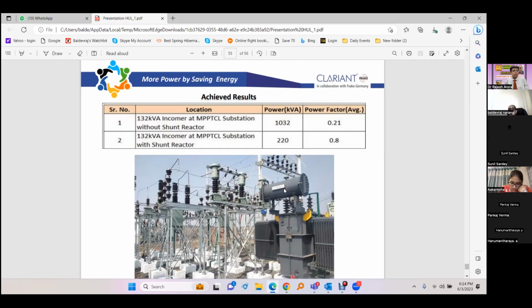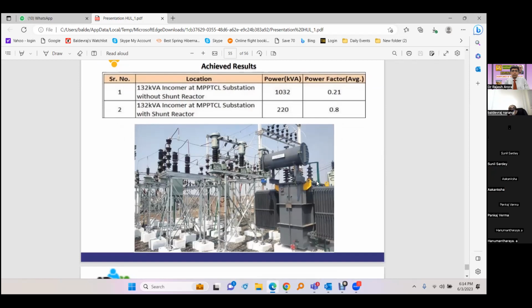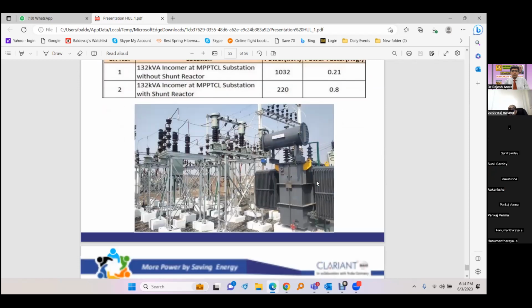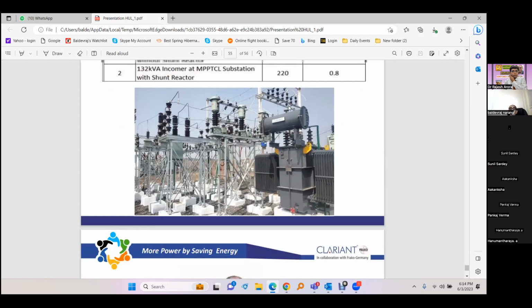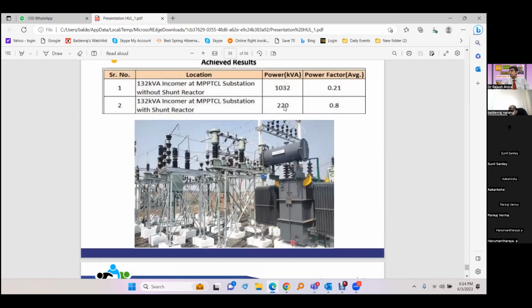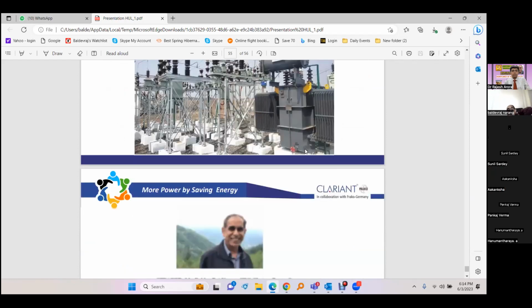And here, by putting this in, we measured the shunt reactor requirement based on the shunt line length, and it was connected on the 33 kV side. And fine correction was done on the LT side in the substation. They could improve the power factor finally up to say 0.9, and the demand was brought down to the normal level of about 130 or 120, something like that. So this is what normally I have.